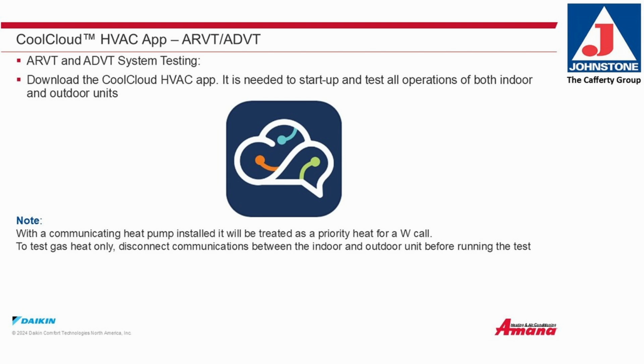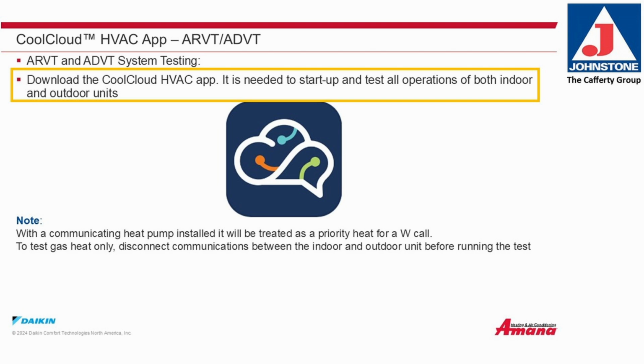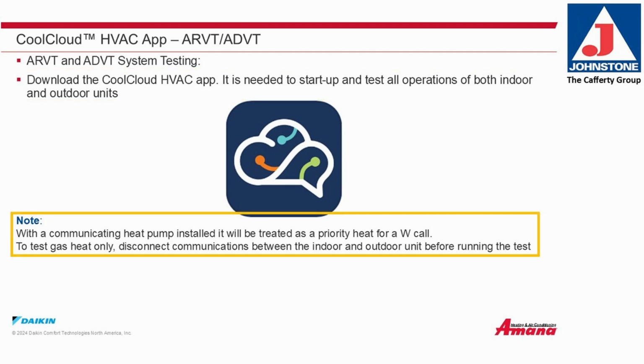Commissioning. The CoolCloud HVAC app, ARVT and ADVT system testing. Download the CoolCloud HVAC app. It is needed to start up and test all operations of both indoor and outdoor units. Please note, with a communicating heat pump installed, it will be treated as a priority heat for a W call. To test gas heat only, disconnect communications between the indoor and outdoor units before running the test.